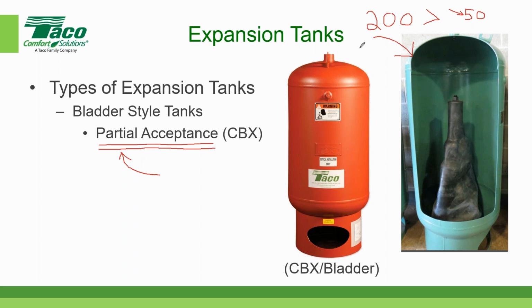Again, like before, you can see the collar that protects the Schrader valve, because the air is added to the top - that's where the compressed air goes. Inside the bladder is where the water goes. Although you can't see it in this photograph, the pipe is actually connected to the bottom, and the water enters the tank from the bottom. If I drew a dotted line here to show it's inside, it would connect to the bottom of that bladder. So that's called a bladder style partial acceptance, and in the world of TACO, that's called a CBX tank.